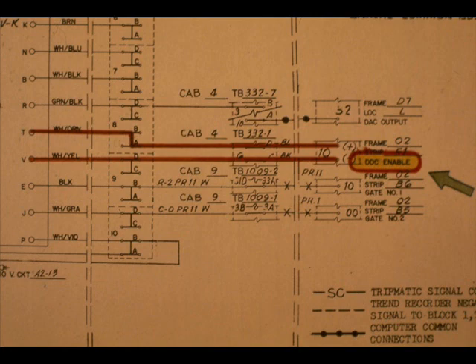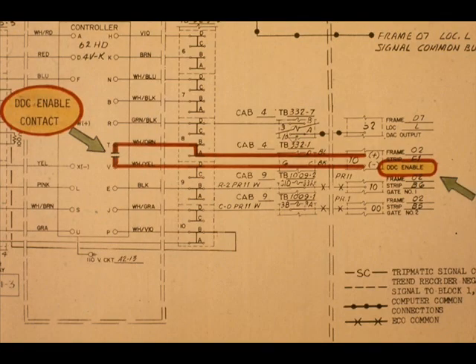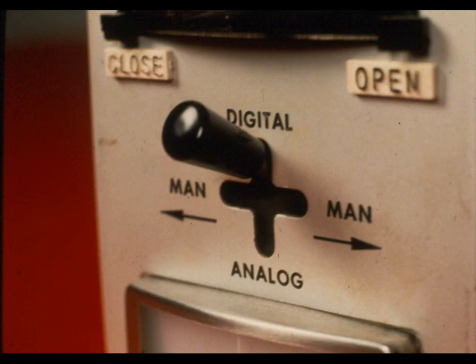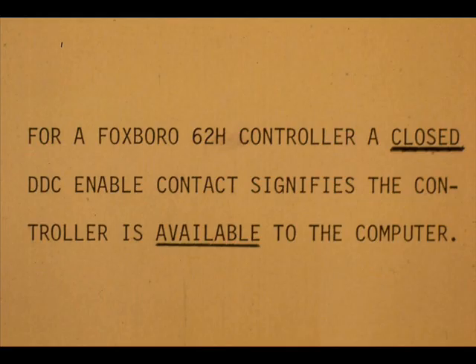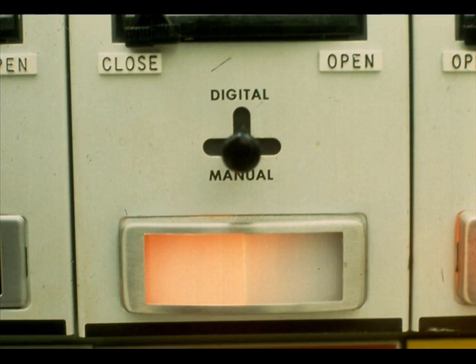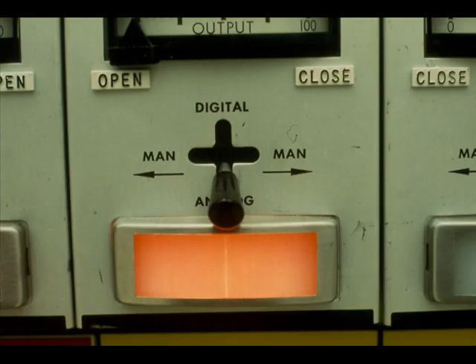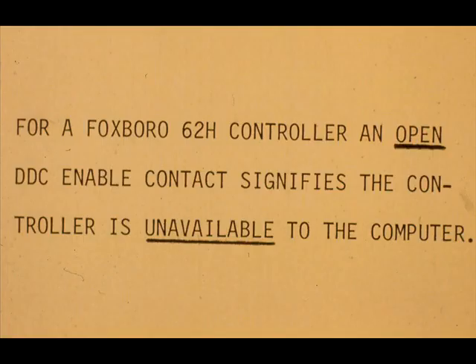The computer receives one more signal from the controller. The signal is called DDC-enable. This signal is produced by a contact closure inside the controller. When the controller selector switch is in digital position, the contact closes. The computer senses the closure and knows the controller is available for direct digital control. If the selector is in manual or analog, the contact is open and the computer knows that it cannot enable direct digital control.